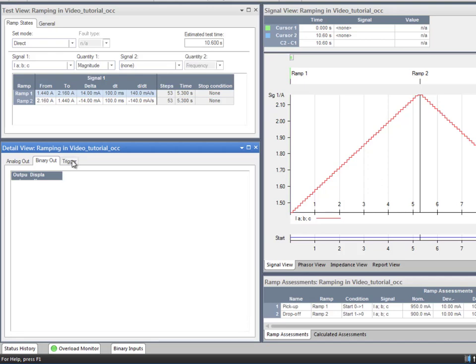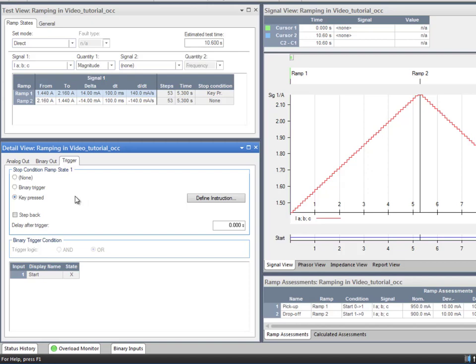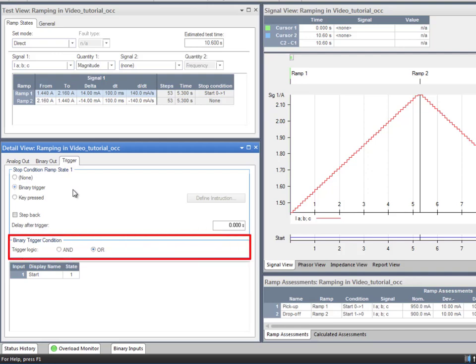Finally, the third tab will set individual stop conditions to terminate the state before it reaches its end value. The default setting is None, that is, no trigger will stop the ramp state. It runs from 1.44 amps to 2.16 amps. The key pressed option enables you to manually trigger the ramp state termination during the test. When the ramp starts, a dialog box will pop up and wait until you press Continue.